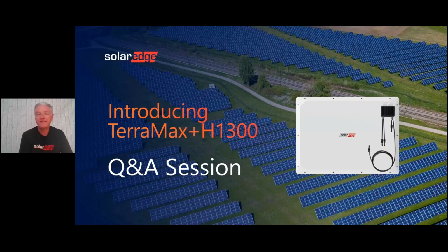Wonderful. Yep. All right. Okay, since the 690 volt AC is not a common service voltage, do all SolarEdge 330Ks require a transformer? So they're meant to be installed in systems that would require a transformer, yes. So 690 volts, being above 600 volts, makes it an 800 volt class inverter. So it's meant to be used with a transformer and connecting to medium voltage in most cases. However, there are use cases where you could be connecting this behind the meter. And in that case, you would need a step-down transformer that would perhaps step it down to 480 volts.